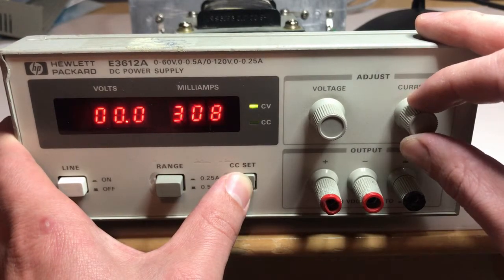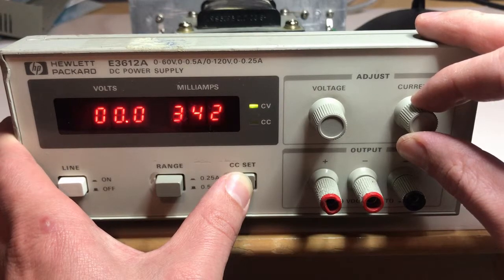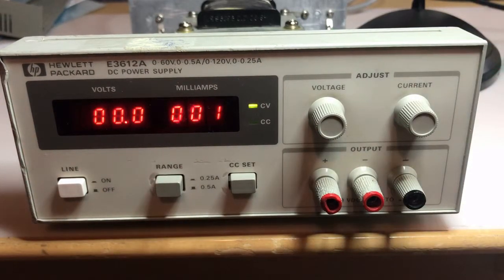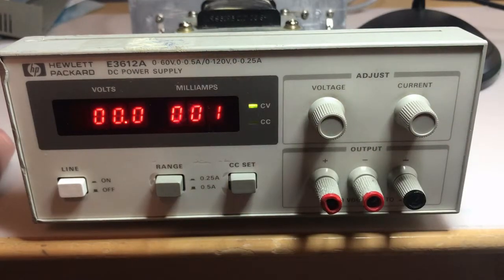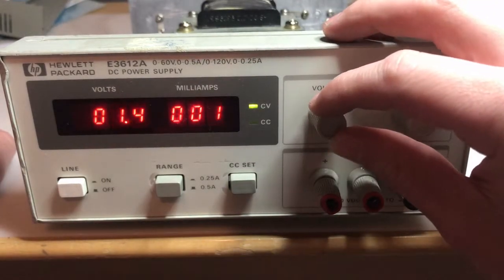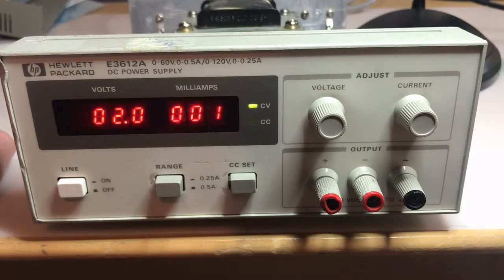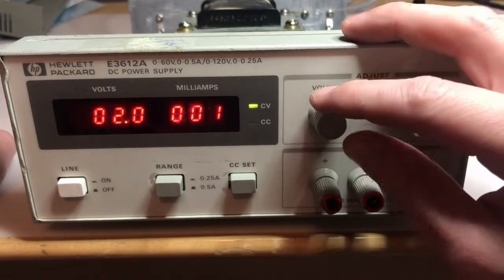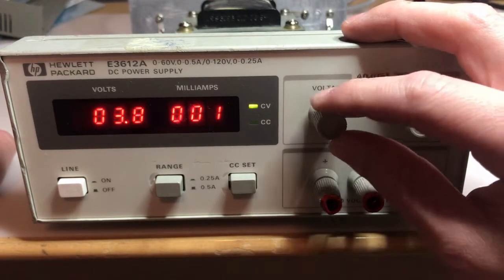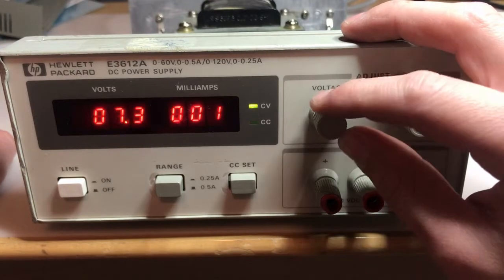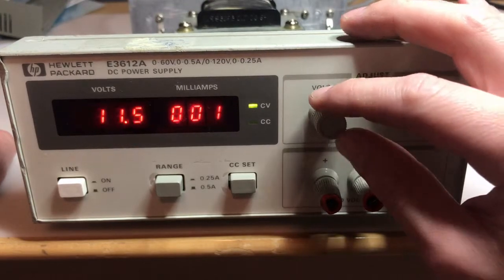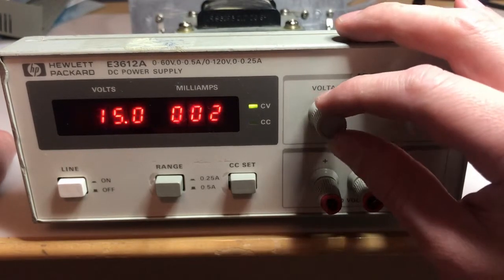But let's tweak this up to 400 just so we can see if we can get an output. Okay, so it's at least reading 0 milliamps output. Let's see if we get a voltage. Much better, I barely turned that and I'm getting an output voltage here of 2 volts, 3 volts. Still not registering anything on the current output, which is good—it's not tripping anything, no shorts.